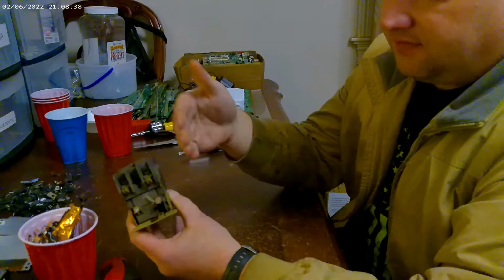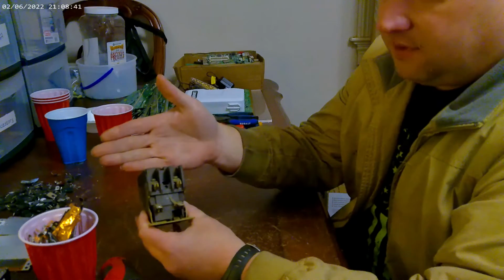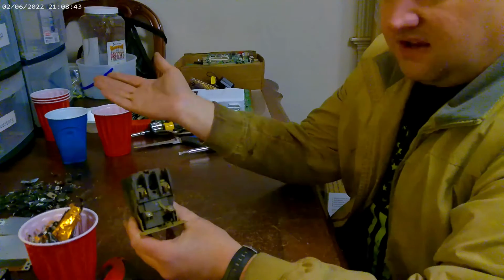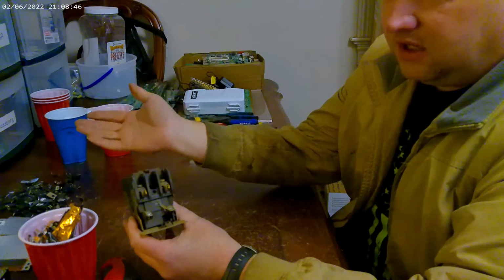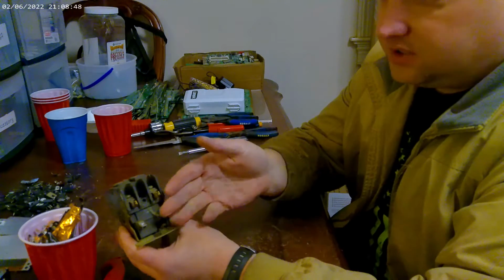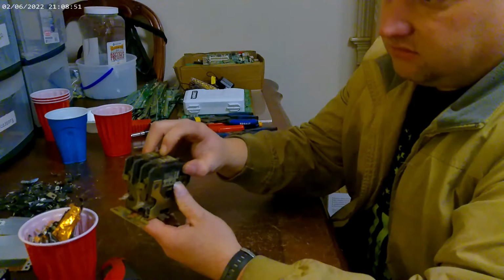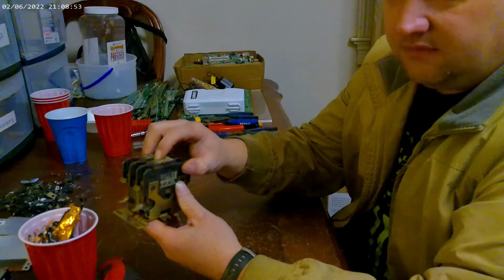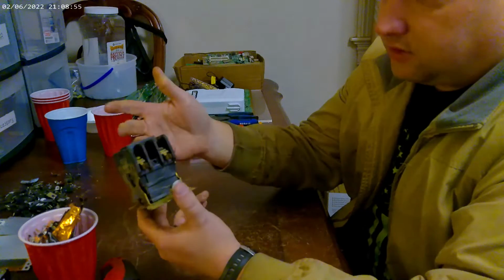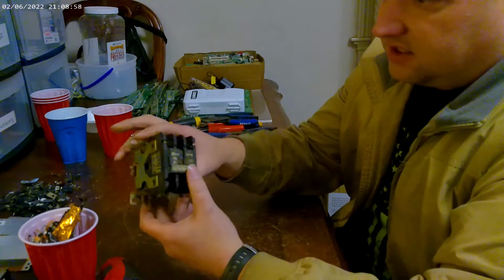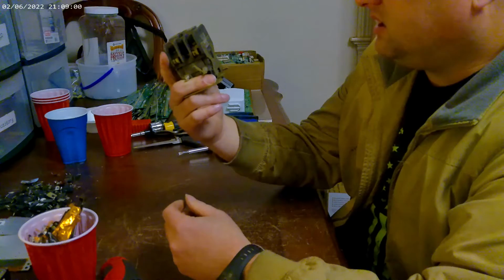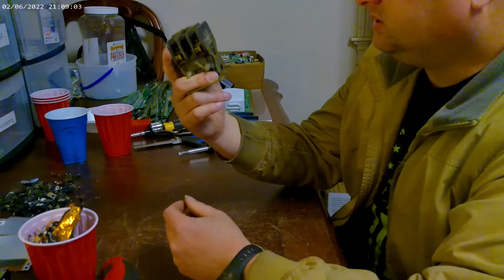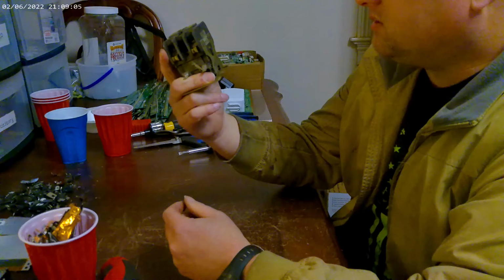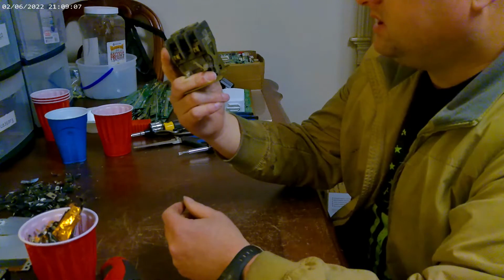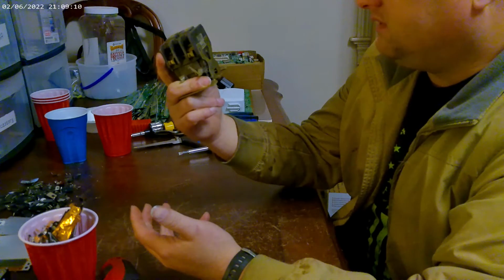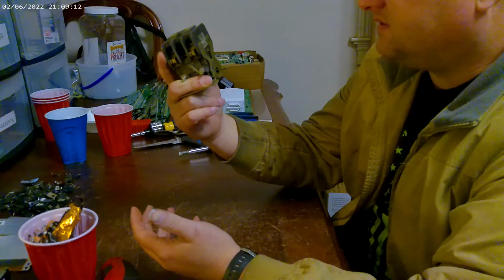So that's how you have control voltages that run high voltages. That same voltage is not in those controls. It's run by low voltage, and the low voltage controls stuff like this to run the high voltage. So this is motor control stuff. It's a contactor. It's actually a Cutler-Hammer. It gives you horsepower rating, voltages. I mean, your voltages, it can run 115, 230, 460, or 575.